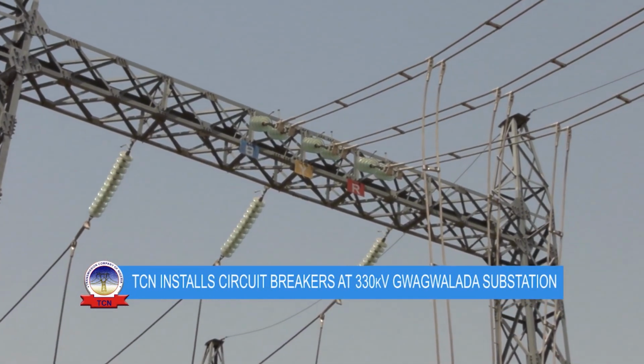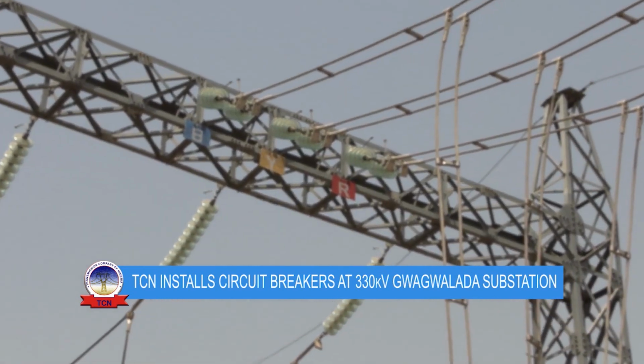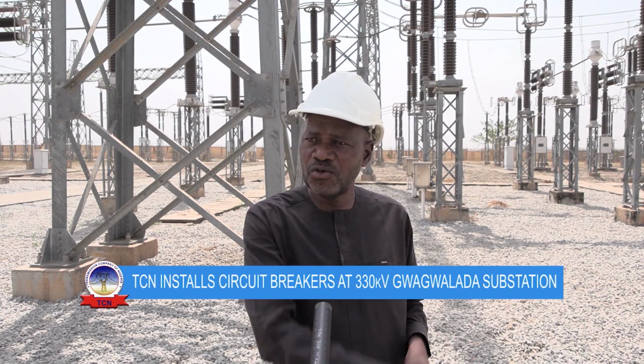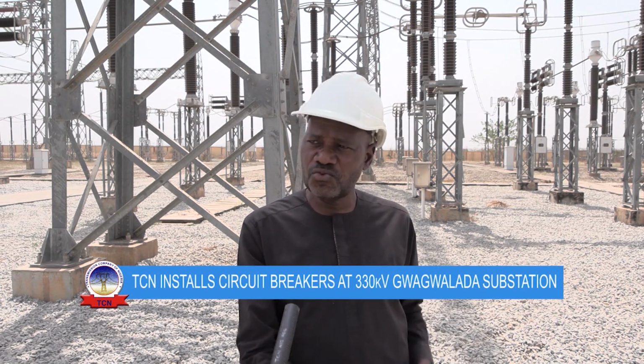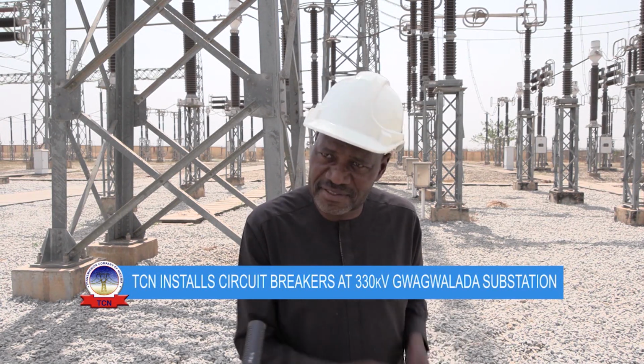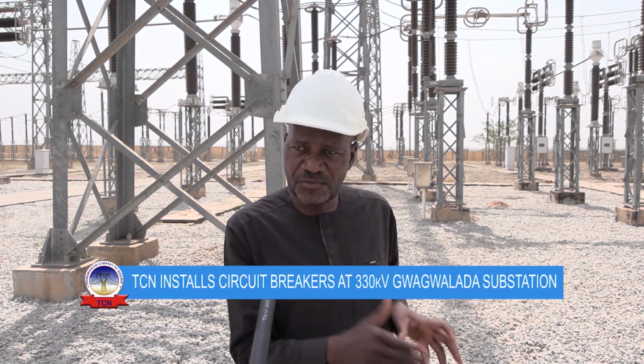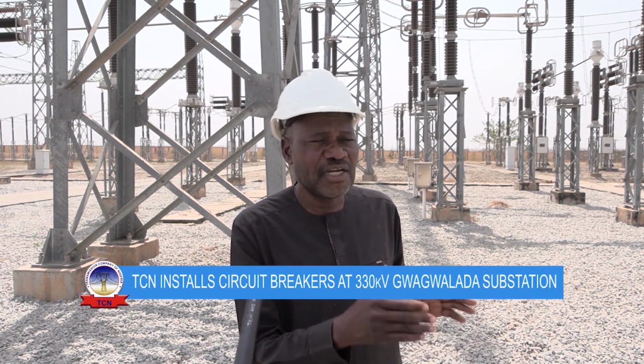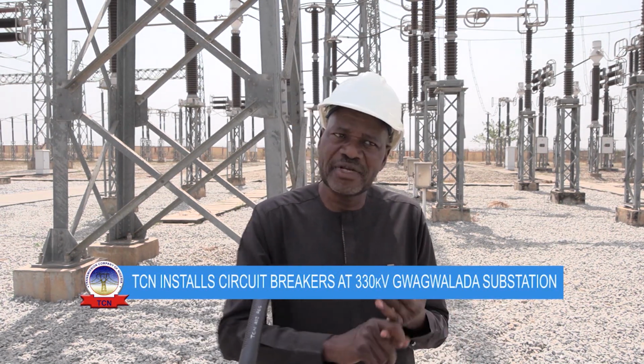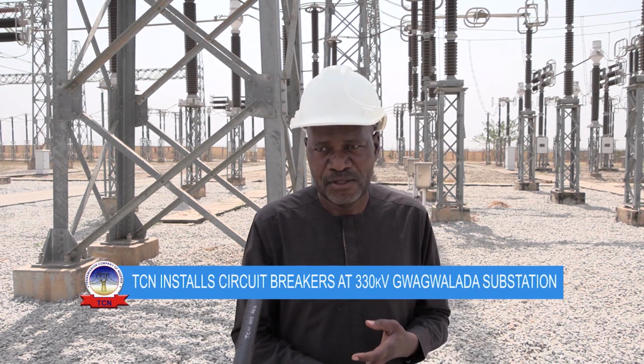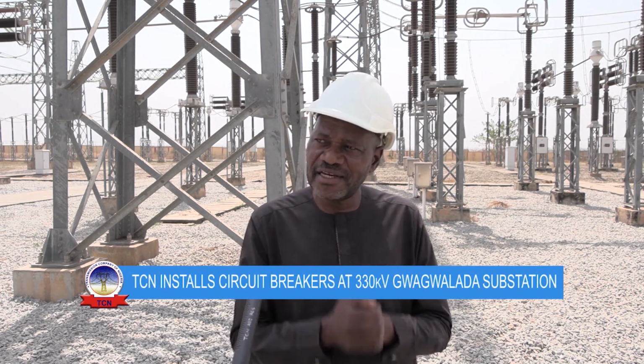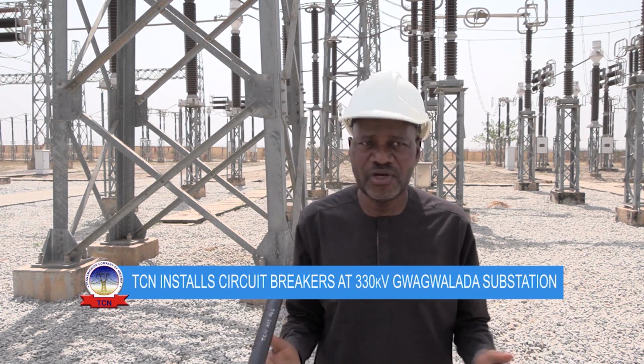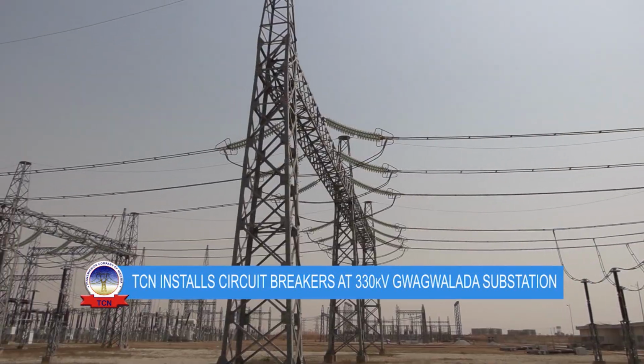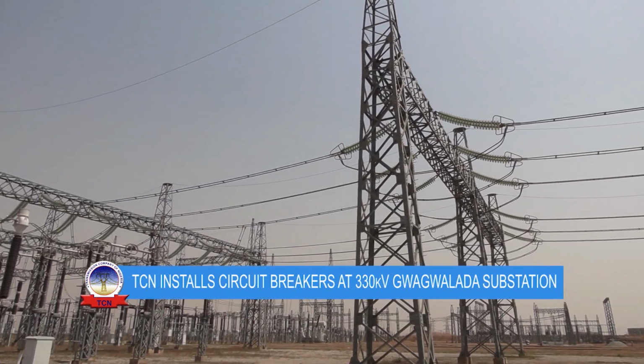With these solid connections to our network, the arrangement of our Gwagwalada substation is a one-and-a-half breaker system. Any line that comes here is connected through two isolators. The design that is economically adapted worldwide is the one-and-a-half breaker system, that's why we had to get a brand new breaker.